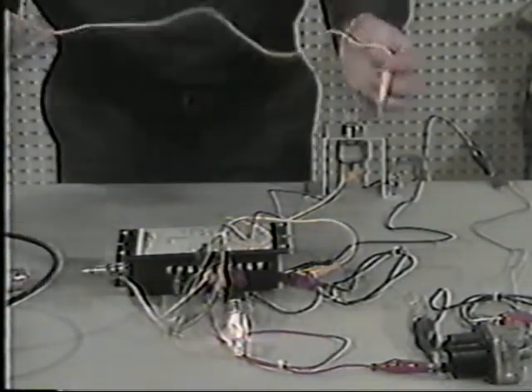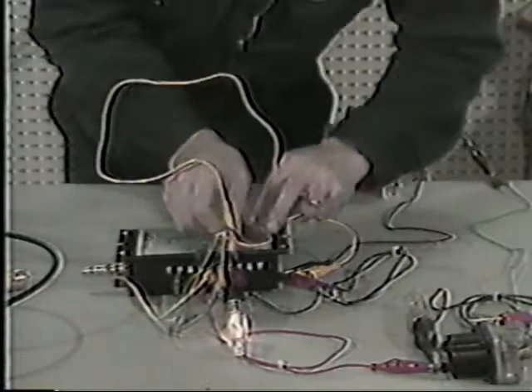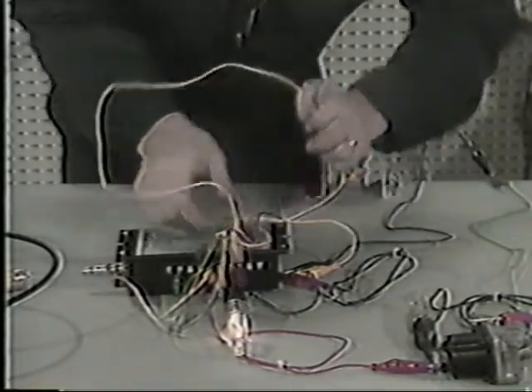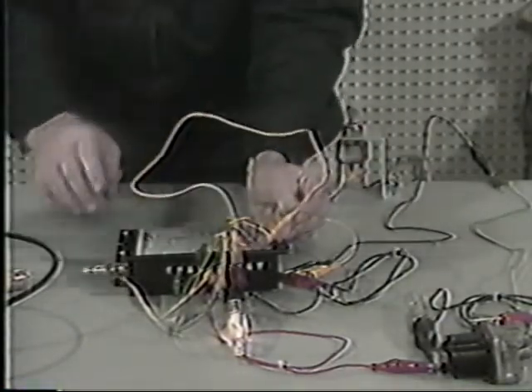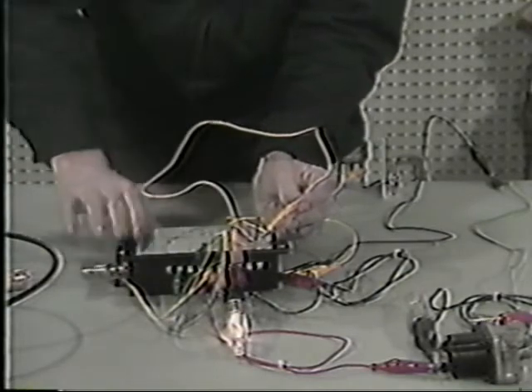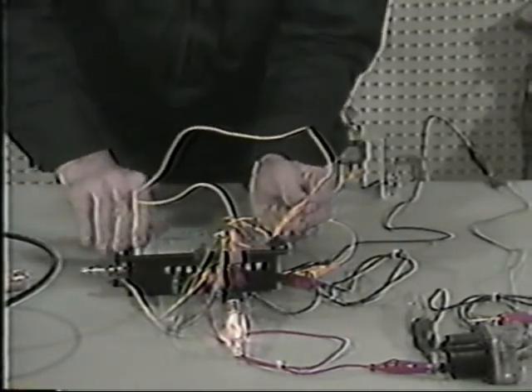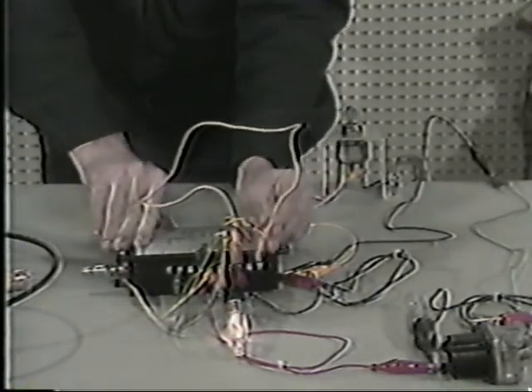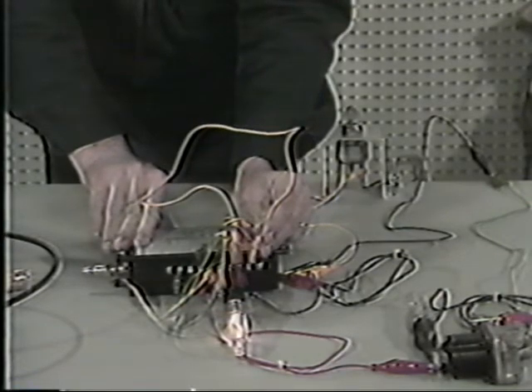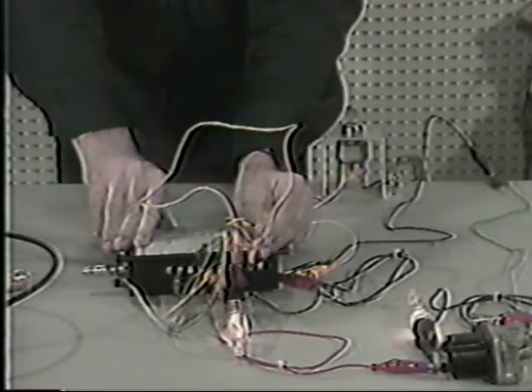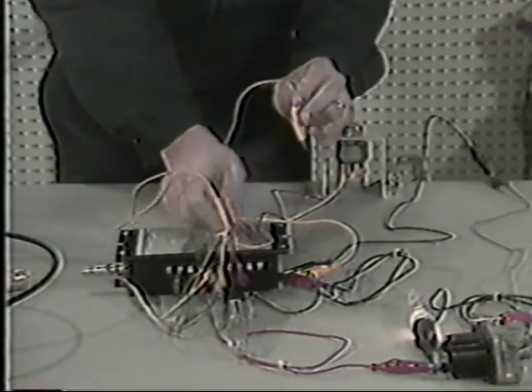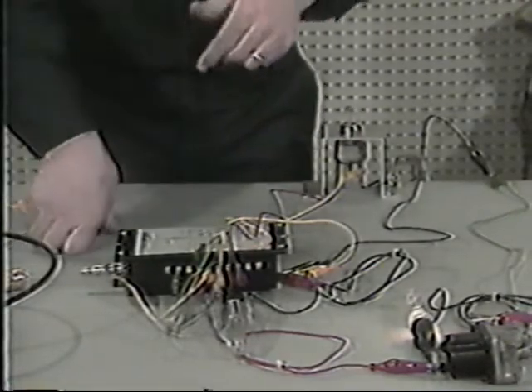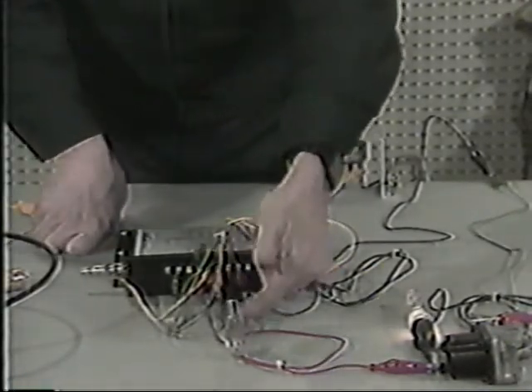Now we must reset the module for our next test. Go ahead and connect the jumper wire to positive. Reach around behind the module here where the reset button is. Push the reset button all the way in and touch the wire to the start terminal. The fuel solenoid again comes on, and when we release the reset button, the warning test light turns off.